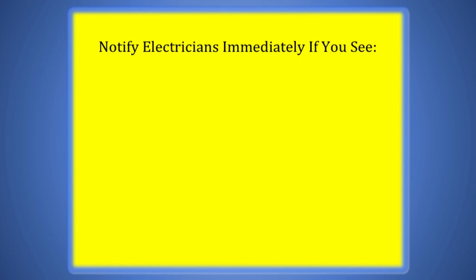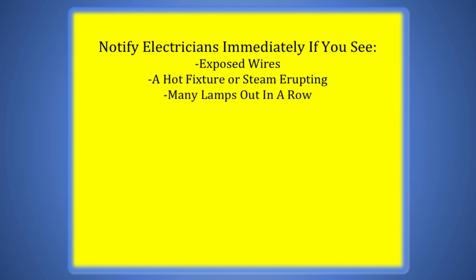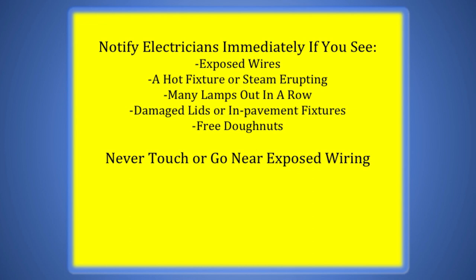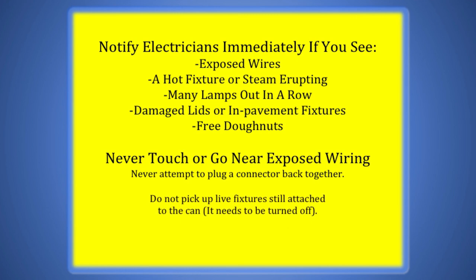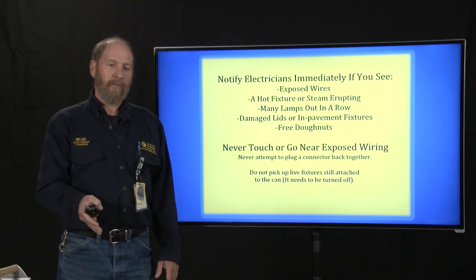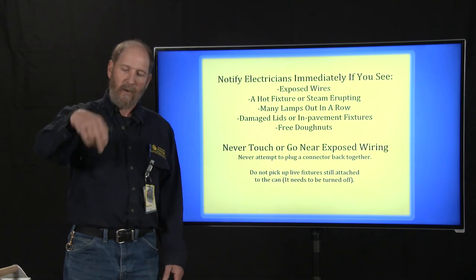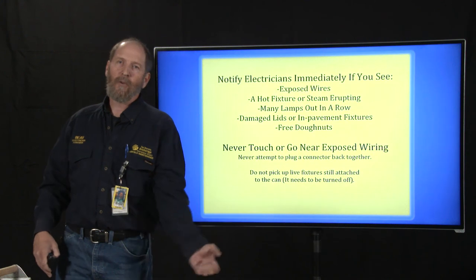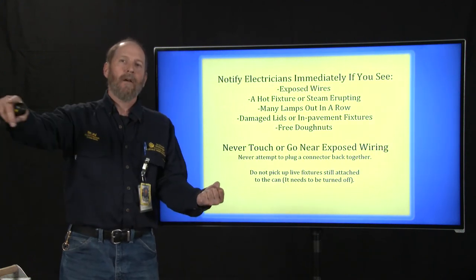So now, some things that you should have learned here. You should notify electricians immediately if you see exposed wires, a hot or steaming fixture, or steam erupting from a can, many lamps out in a row, damaged lids or in-pavement fixtures, free donuts. Now, if you call the electricians every once in a while because there's free donuts, that means they will answer the phone every single time you call, so it's important. Never touch or go near exposed wiring. Never attempt to plug a connector back together, especially a live connector. Don't pick up fixtures that are still attached to the can on a live circuit. So if a taxiway edge light is broken free from its frangible and it's laying there but still attached to the can, make sure the circuit is dead before you grab hold of that light, because it could have a short going to the can.